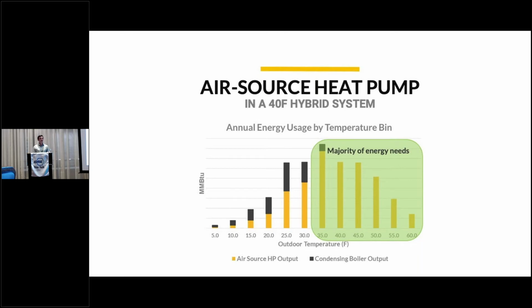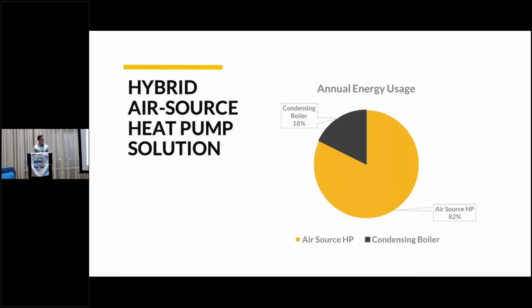And then what we did is we put this into a pie chart. And this is really compelling because even though we only sized our heat pump down to 40 degrees Fahrenheit, we're able to cover 82% of our building's energy usage from that heat pump. And then our condensing boiler is only running 18% of the year.